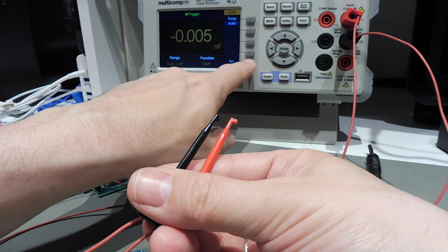Again, be careful when measuring capacitance in a circuit. It's much better to use a specific device for that, because they use much lower voltages. Also, when you connect the capacitor, make sure it's discharged properly. Half a volt probably doesn't matter, but if you have something with 10 volts or so on it, discharge it beforehand, because you might destroy the input circuitry of your meter.